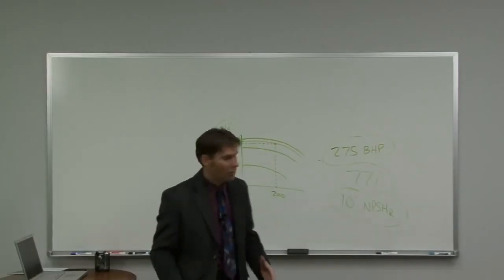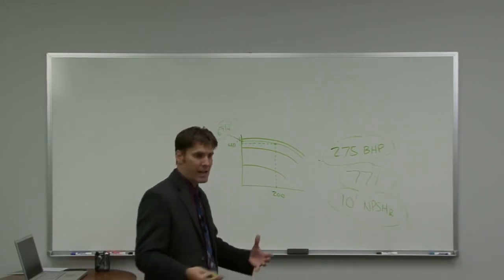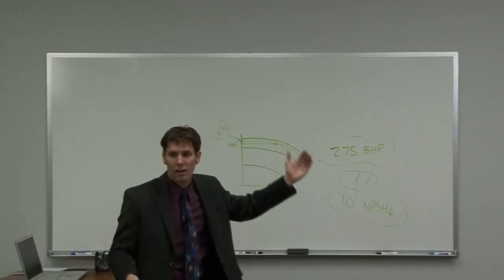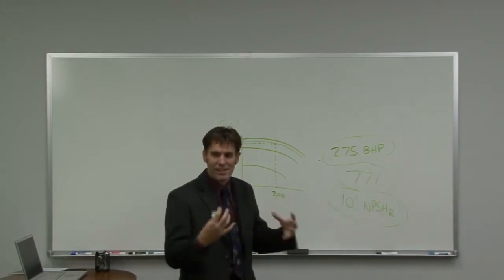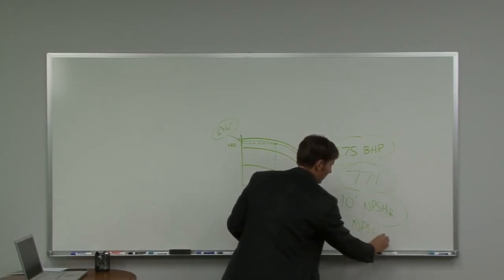Now, I'll tell you this right now. Most closed-loop hydronic systems that are closed to the atmosphere are pressured to some given pressure, maybe up to 12 psi for a single or 2-story building. We get into a high-rise. This high-rise might be 20 stories tall. You're going to have a lot more pressure. We're going to have so much pressure in these closed systems that when we calculate our NPSHA, you're going to have so much more suction head available.